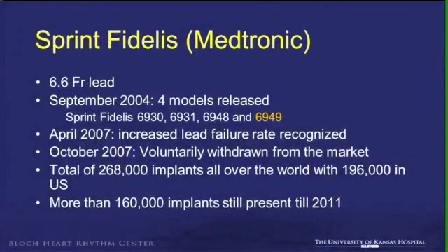So I'll start off with the Sprint Fidelis lead, which is a Medtronic lead. It was marketed in September 2004. Very popular lead. At that time the lead size was a pretty good marketing point. It was very attractive. The smaller the lead, the easier it was for the physician to implant. So it was one of the smallest leads at that point of time, and a lot of leads were implanted. In April 2007, there was a confirmed recognition of increased failure rate. And in October, it was voluntarily withdrawn from the market.